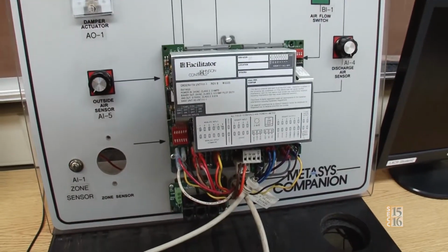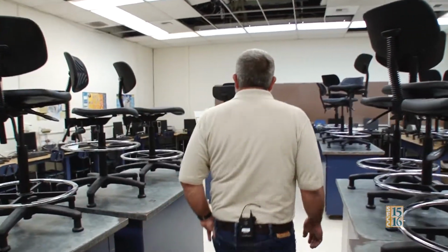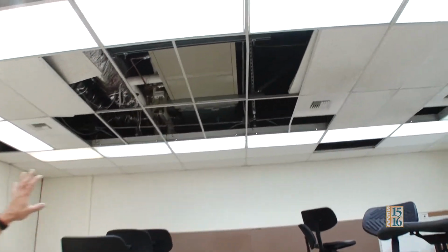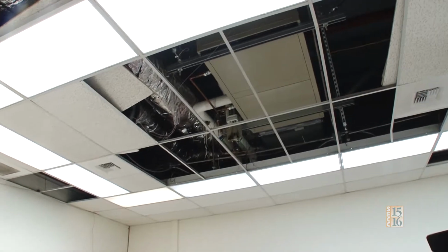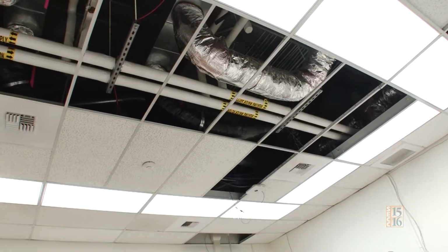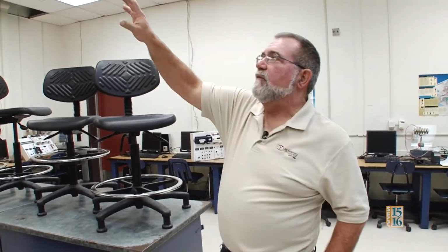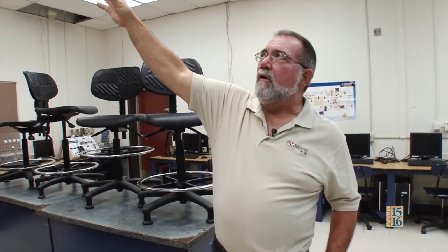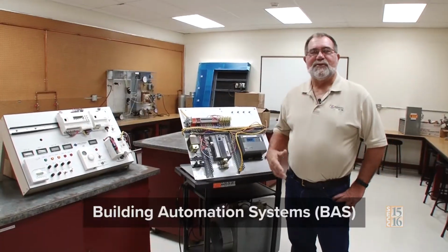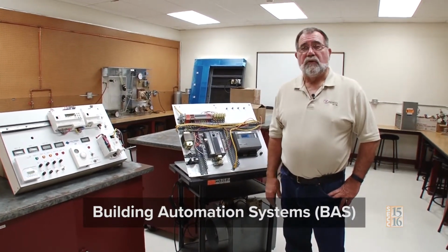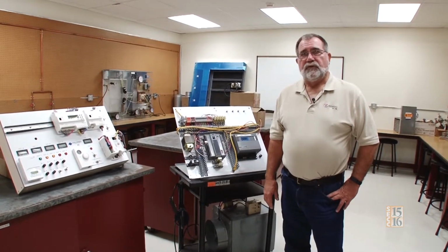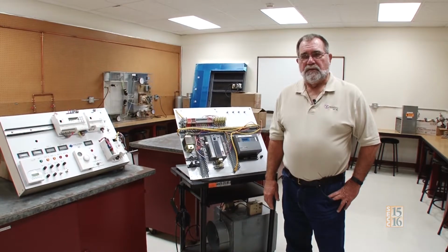And the air handler, okay, so this air handler up in the attic space, we also control that air handler. And that one, the heating and cooling comes from our boiler plant and from our chiller plant. The other thing we have up here are VAV boxes. The students can go on to the Metasys program, they can adjust the airflow, and then they can come back and actually take physical measurements of what the airflows are at the register and compare them to what the readout is on the BAS system. So in this room, the students learn the theory behind automated controls, and then they also learn how to adjust them and set them up to meet the demands of the building.